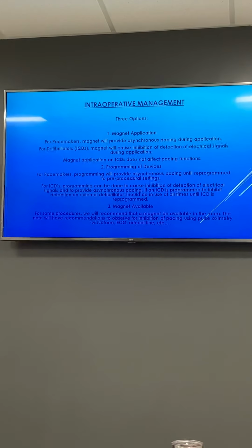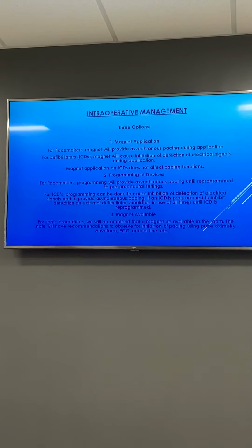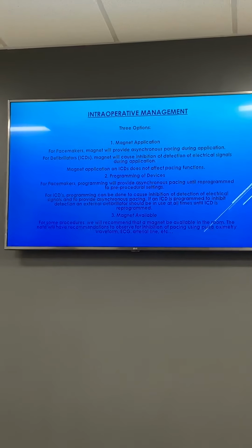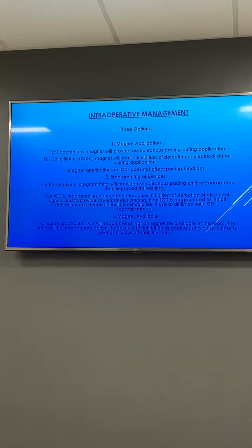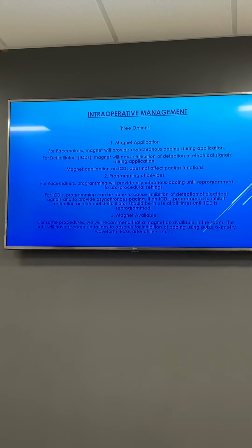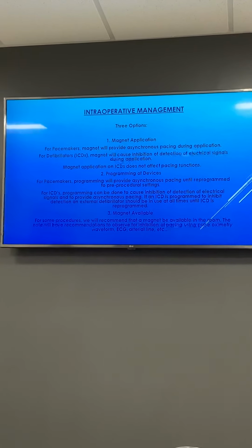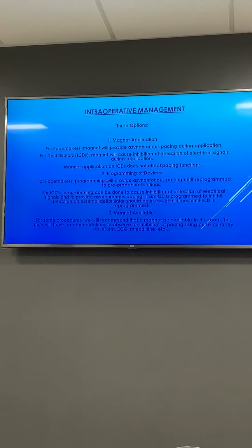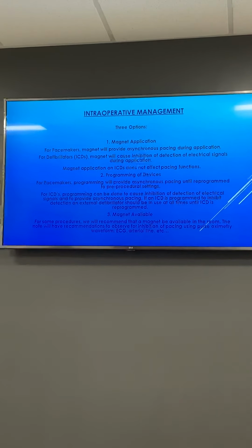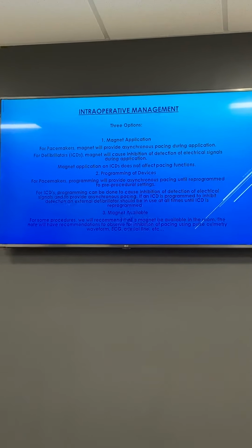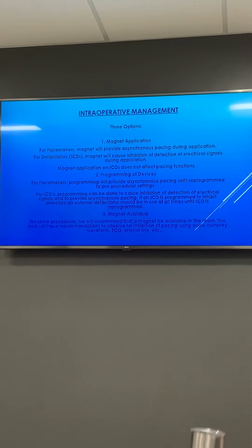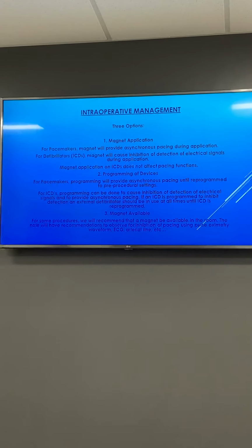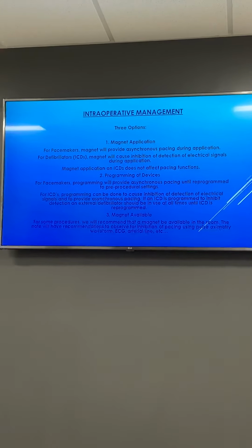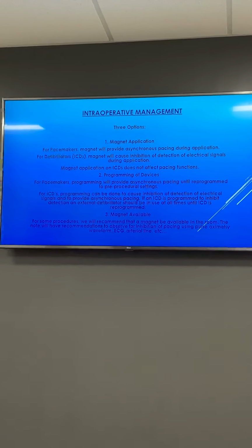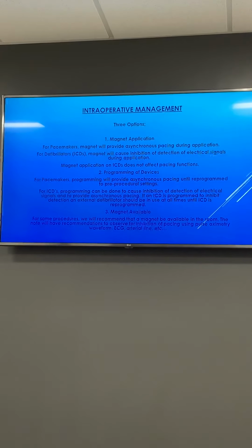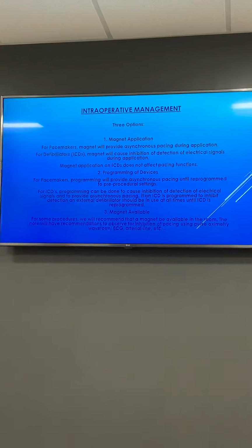The three options that you will see, I will say place a magnet over it. For pacemakers, when you put a magnet on top of it, it makes it pace no matter what it sees. Pacemakers are basically a little timer for the heart. It looks for, in milliseconds, a certain beat that we have set. If it doesn't see that, then it paces. When we put a magnet on it, it's gonna pace at the set beat.